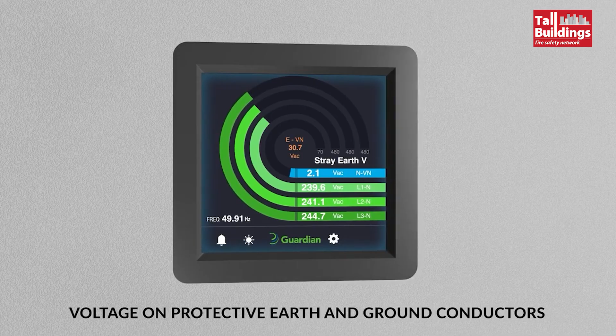The Guardian can connect to a web-based portal where each device can be viewed remotely. Alerts of any detected faults can be sent to the building user or maintenance company to help warn them before catastrophic failure occurs. With the Guardian installed, monitoring the supply and the building's electrical infrastructure, your building will have 100% detection and protection against the dangers caused by broken neutral faults.